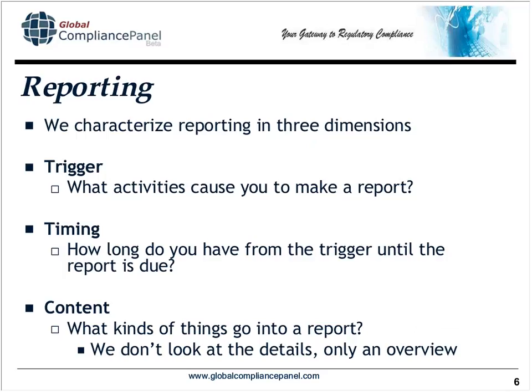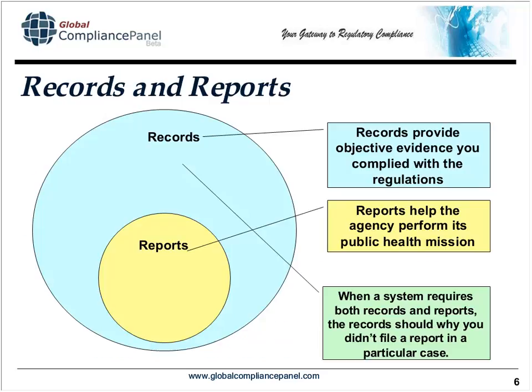In contrast to records, which are things we keep for ourselves to demonstrate objective evidence that we follow the quality management system, sometimes we have to tell the regulatory agencies that we've actually done something — I'll call that reporting. I'll characterize reporting in three dimensions. The first is the trigger: what activity causes you to make the report. The second is timing: very often regulations specify a timeframe from when the trigger occurs until the report is in the hands of the regulators. The third is content: what kinds of information go into the reports.